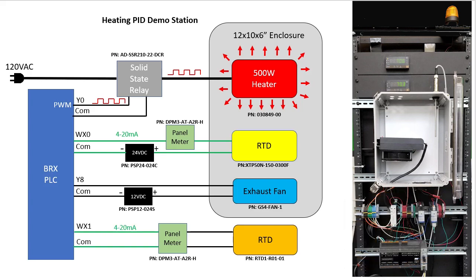I connected another digital panel meter to a room temperature RTD sensor and sent that into another BRX analog input so we can monitor the temperature of the room during our testing. This panel meter is both showing me the room temperature and converting the RTD signal to 4 to 20 milliamps, which saves me from purchasing a BRX RTD input module.